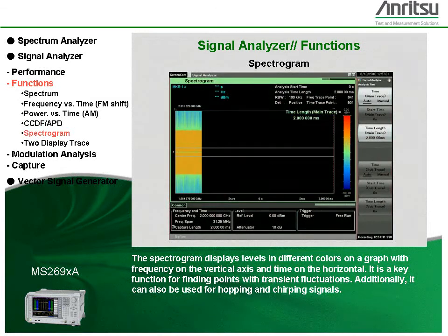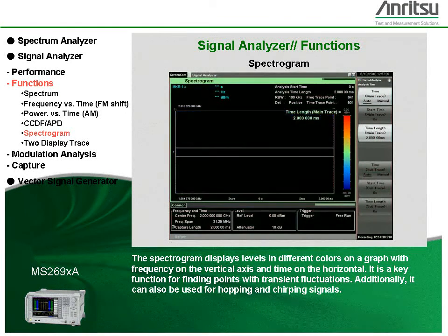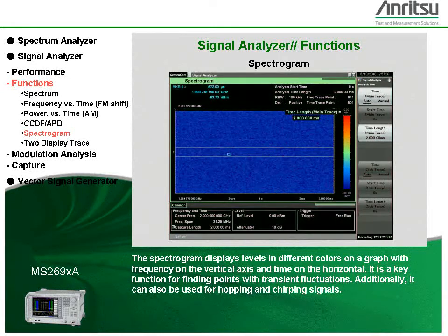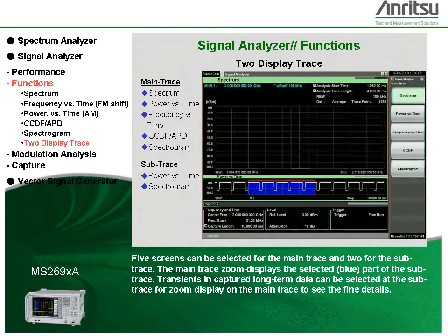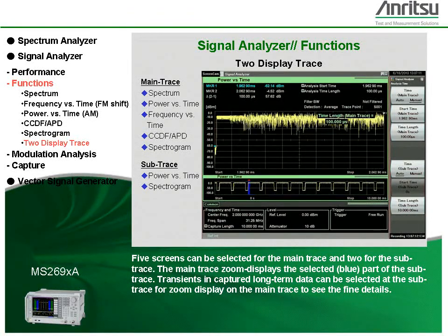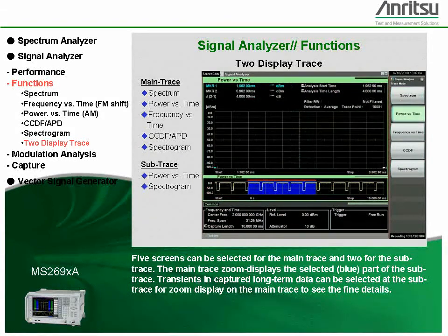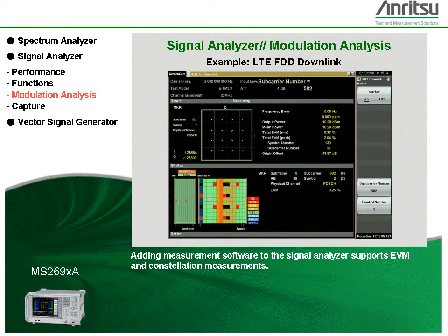The APD display indicates the probability distribution of transient power fluctuations compared to average power. The spectrogram displays levels in different colors on a graph with frequency on the vertical axis and time on the horizontal. It's a key function for finding points with transient fluctuations, and can also be used for hopping and chirping signals. Five screens can be selected for the main trace and two for the sub-trace. The main trace zoom displays the selected blue part of the sub-trace, allowing fine detail viewing of transients and captured long-term data. Adding measurement software to the signal analyzer supports EVM and constellation measurements.